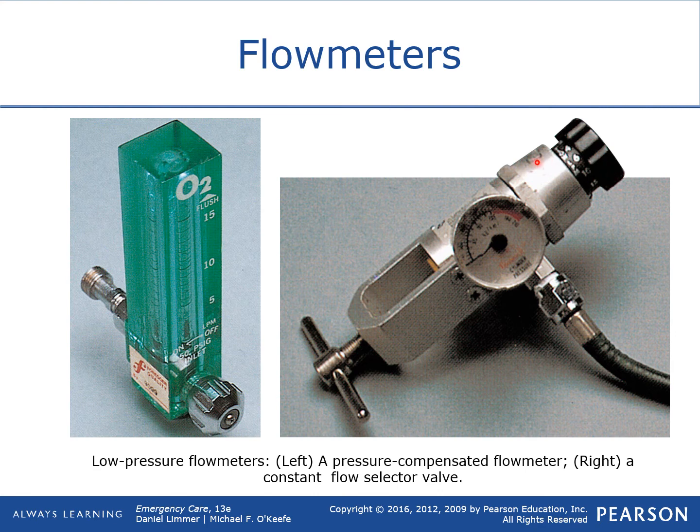Right here, this guy is a typical one that we see on a portable tank. So you have your pressure gauge right here. Then this dial right here, you twist. You can see 4 and 6, 10, 15 on there. You just twist it to, there's usually an arrow marking either here on the side or on the top. You just twist until that number gets to the arrow that you want, and that's the amount of liters that you're putting out.